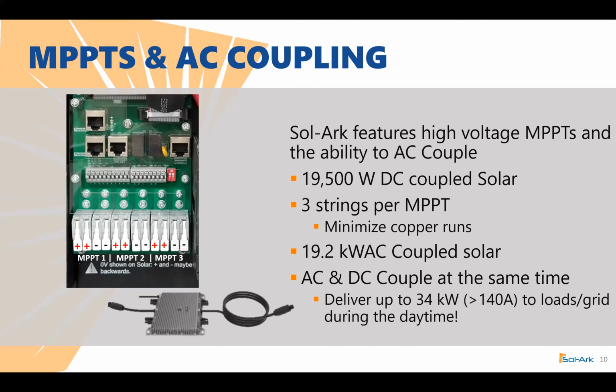We can connect up to 19.5 kilowatts of DC coupled solar at the MPPTs. And then for the AC coupling portion, we can actually connect up to 19.2 kilowatts simultaneously. So with the AC and DC fully maxed out, you can actually get up to 34 kilowatts of sell back to the grid or to the loads during the daytime, and even in an off-grid situation. As long as the battery bank is at a lower state of charge, the entirety of the DC and AC array will be utilized.